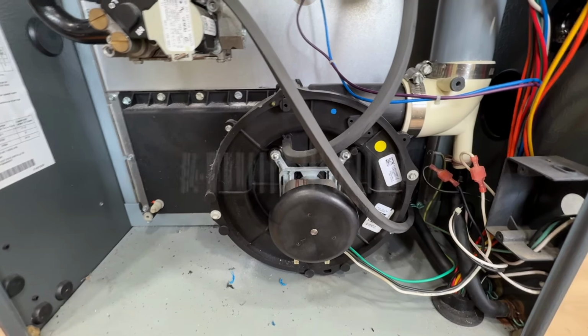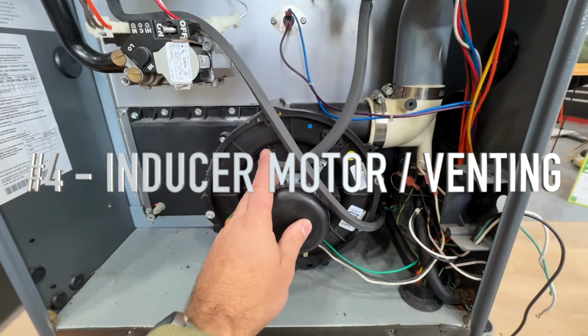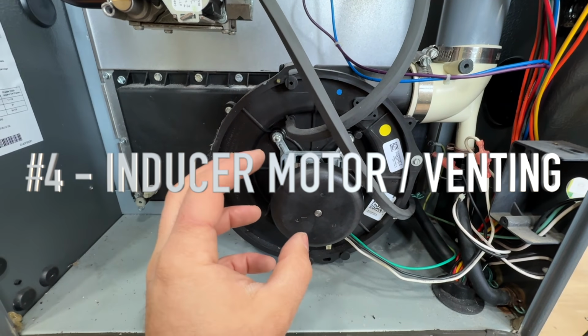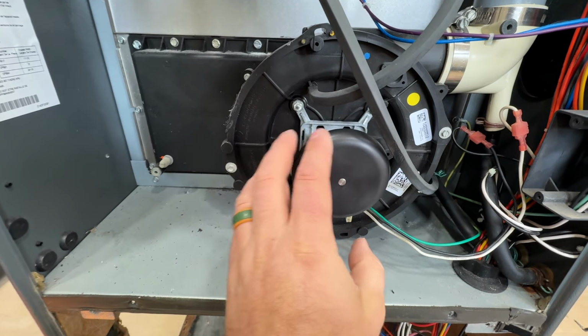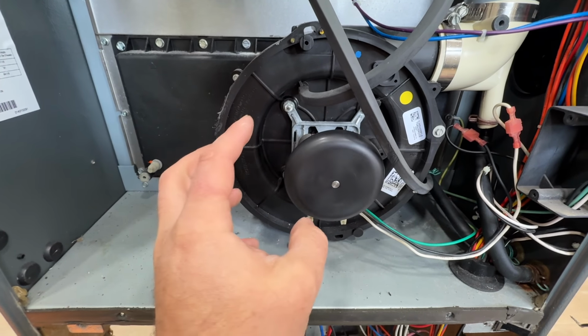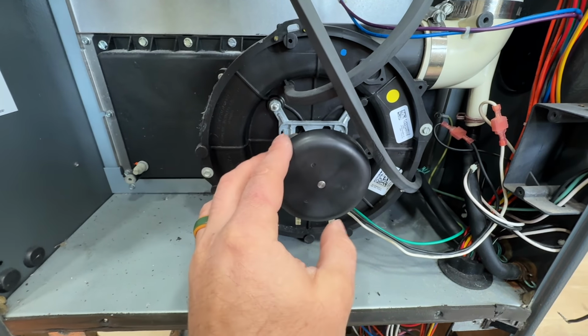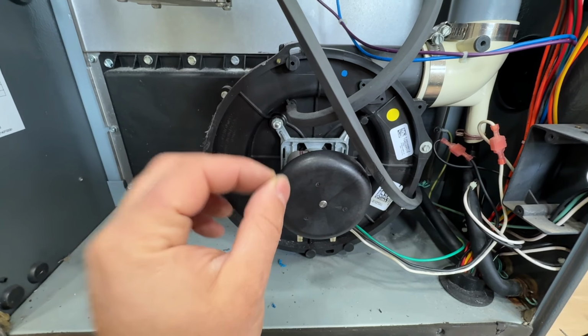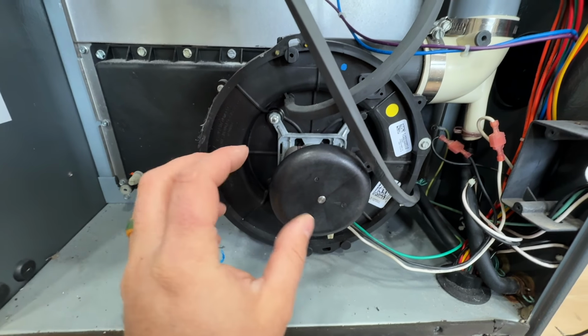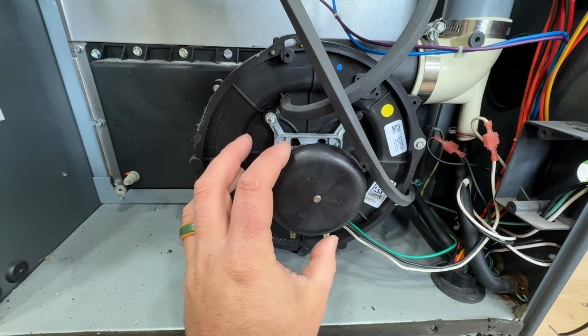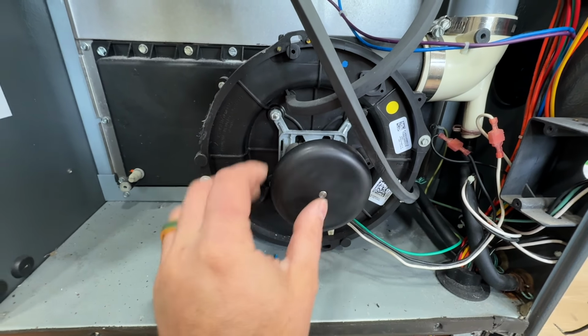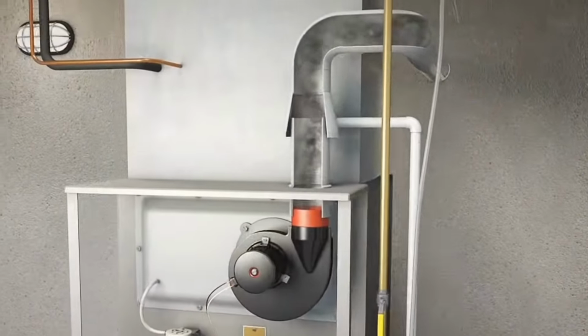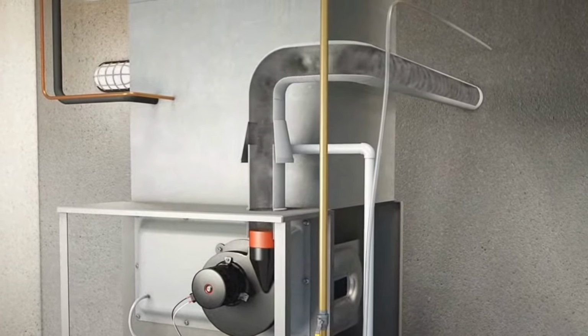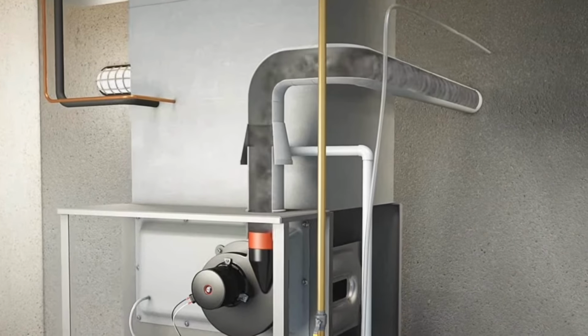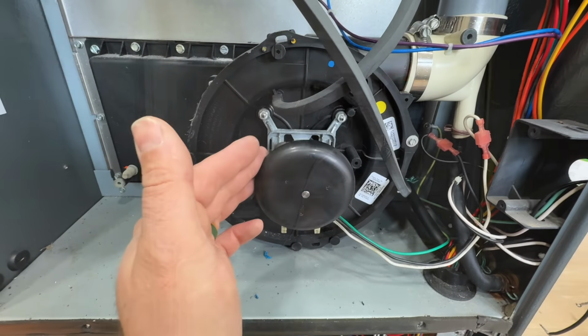Number 4 has to do with the inducer motor. Now, just the obvious things, if you go down here to your furnace, this is the first thing that will come on. And when this is running, it should sound pretty smooth. You shouldn't hear any metal on metal, grinding, things of that nature. If you hear that, probably that's going to be your culprit, because if you have something that's slowing this down and not allowing enough air to be pushed out, your pressure switch is going to be tripped, and that's going to cause the furnace not to turn on.